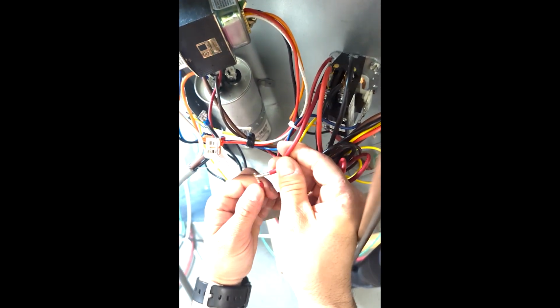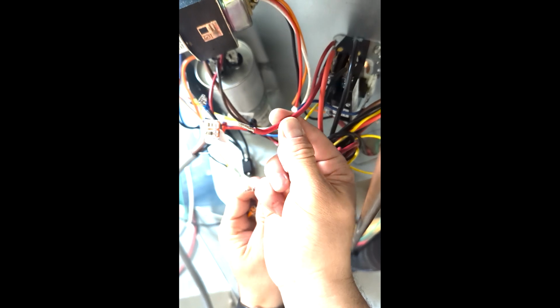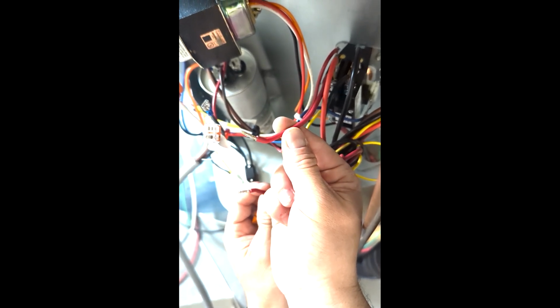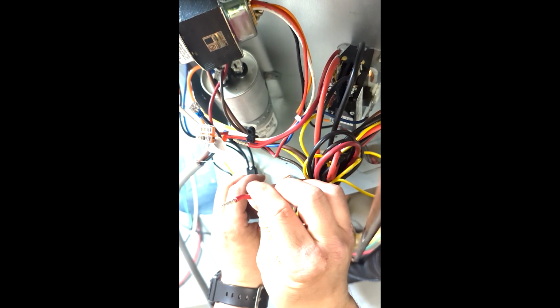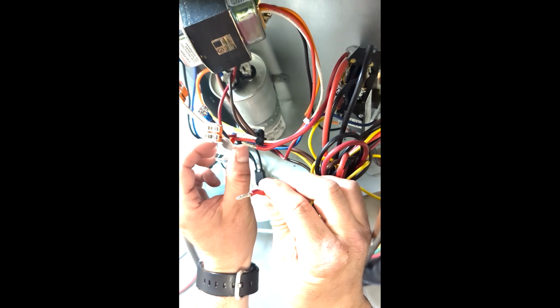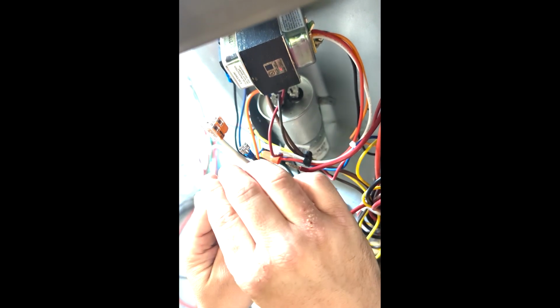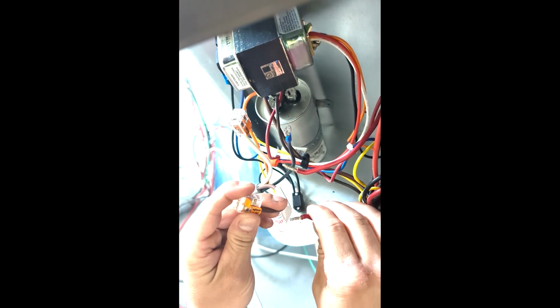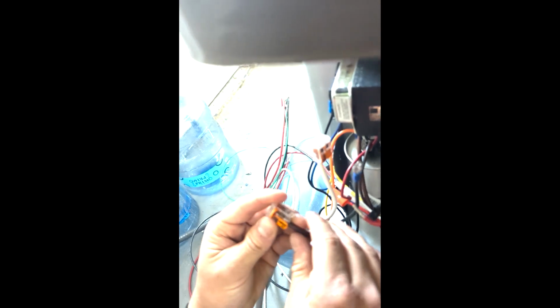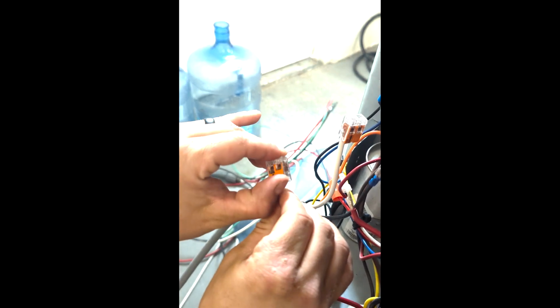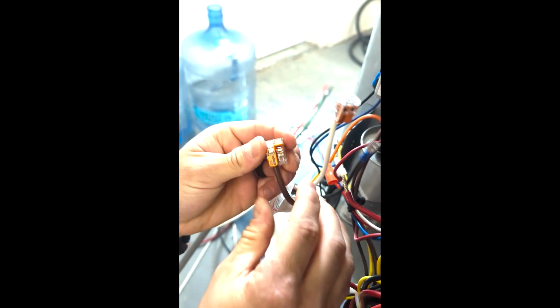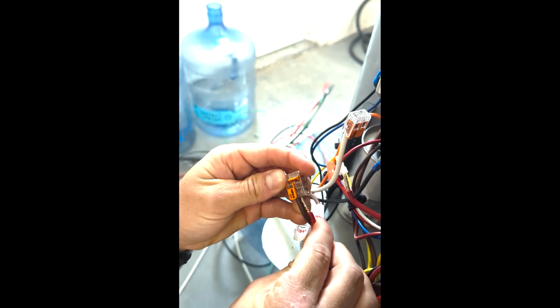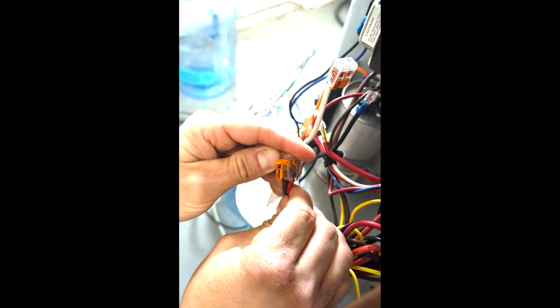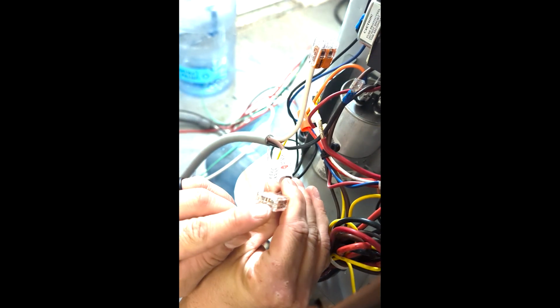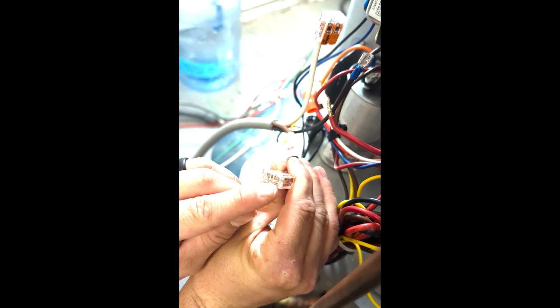What you're going to do is cut that wire in half, okay? Now you have two separate wires here. The one red wire that goes back to your compressor is going to get connected to the brown wire on the EasyStart, okay? And it has this cool WAGO on here. You just flip the tab all the way up, that opens it up, and then you stick your wire in all the way back. One way you can tell is you can see the wire pushed in the back there, okay?